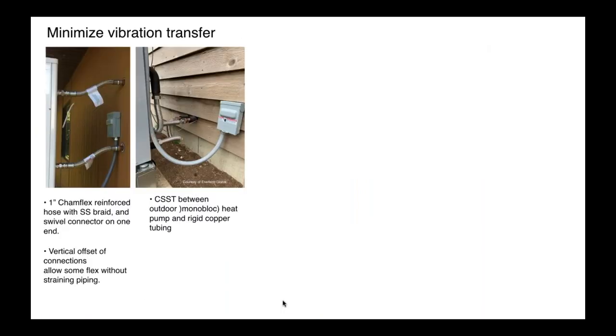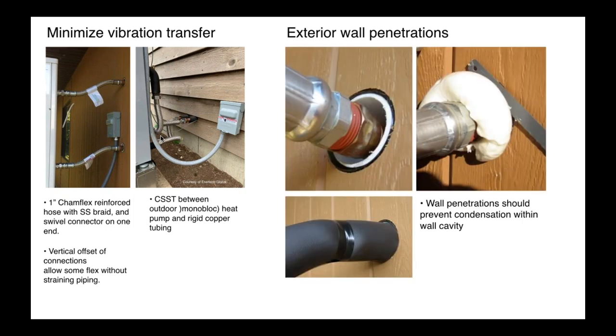Okay. Piping details. I'd like to use either a flexible hose connection like this. This installation used a corrugated stainless steel tube. But what we're trying to do is put some curvature in a flexible tube so that we're reducing any vibration from the outdoor unit transferring to the piping inside. My experience has been that the scroll compressor units that use inverter speed control are much quieter than the on-off units. But in either case, a good anti-vibration detail is good.